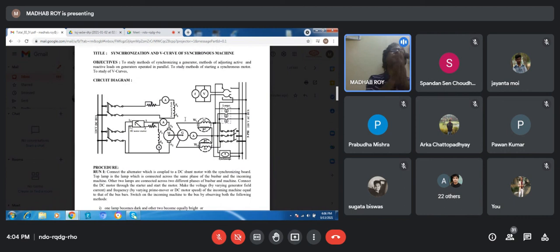Now you are increasing the delta. Then once upon a time the south pole of the rotor will not be under the north pole of the stator where it was earlier. It will shift to the next pole, and thus it will slip. This is called the slipping condition, or out of step. It happens when we increase the loading, because a synchronous reluctance motor cannot take that much loading.